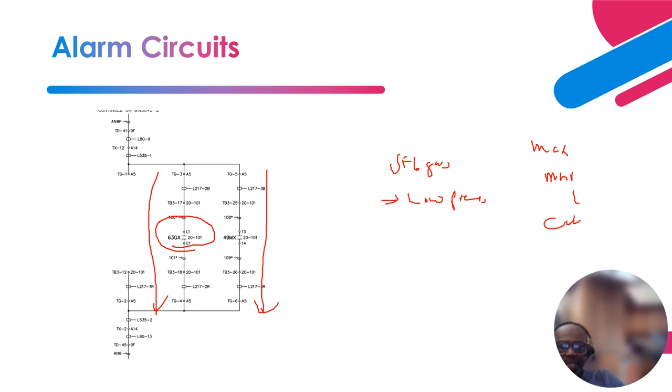Okay, so when the pressure drops below the maximum, towards let's say the middle, towards the minimum, that is when you can set your threshold for your alarm. It's basically subjective. You have to determine the level of gas pressure. And sometimes you can have nuisance alarms based on weather changes. One thing about SF6 gas is that during cold weather it shrinks. Because of the extreme cold, it can drop below the maximum towards the minimum, right?